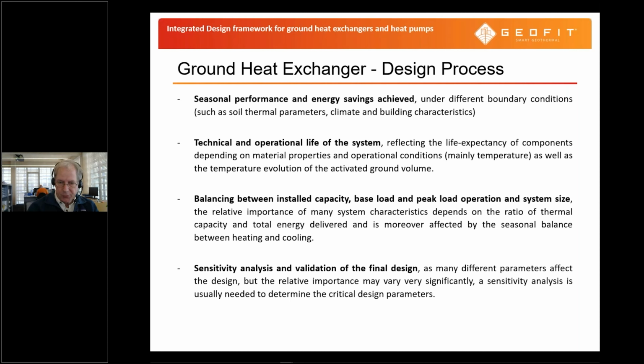At the end, we want also to look at the sensitivity and the final validation of the final design, because we have to make a lot of choices, and some of the aspects we're quite sure about, other aspects perhaps we are not so sure about, and we can investigate how this would affect our design and then decide if we want to have a better analysis of that part of the system. This can be the geology, the thermal characteristics of the ground, but quite often we also find that, for instance, the energy demand analysis of the building is lacking in detail and in quality.